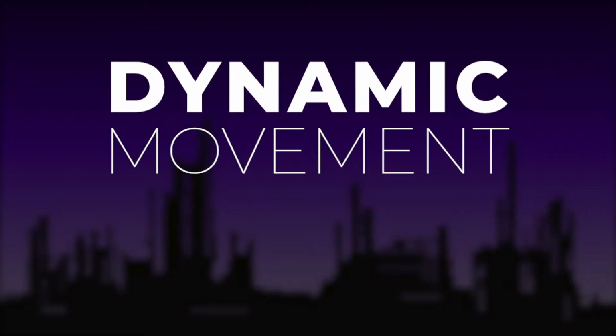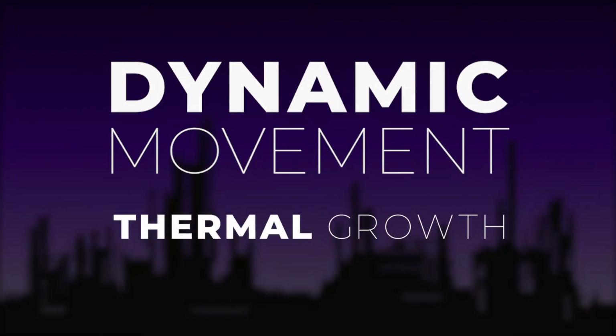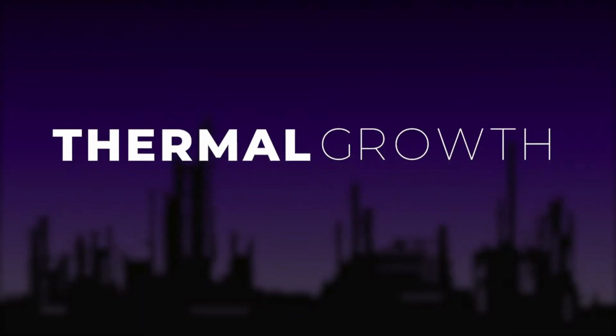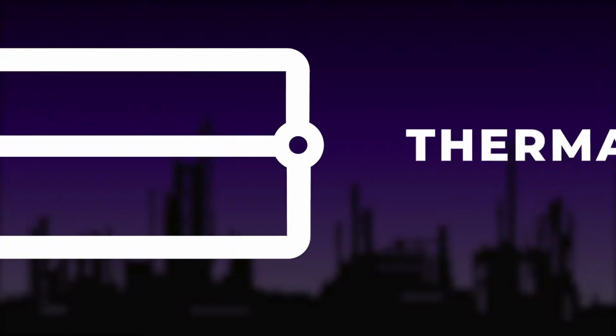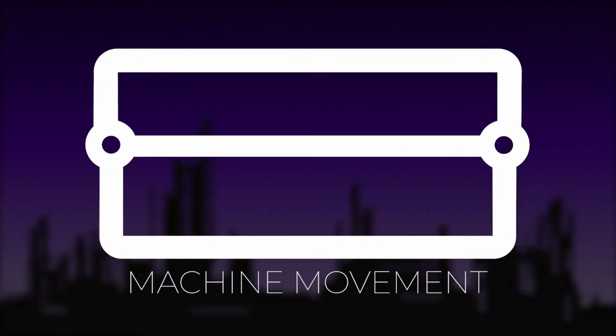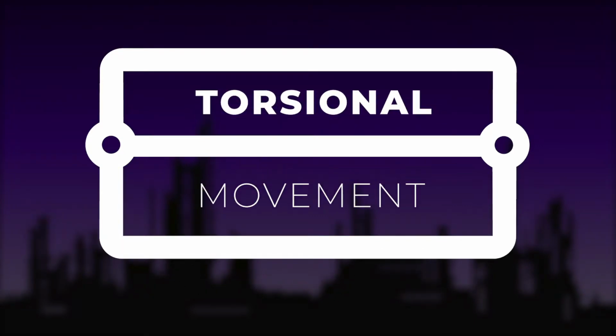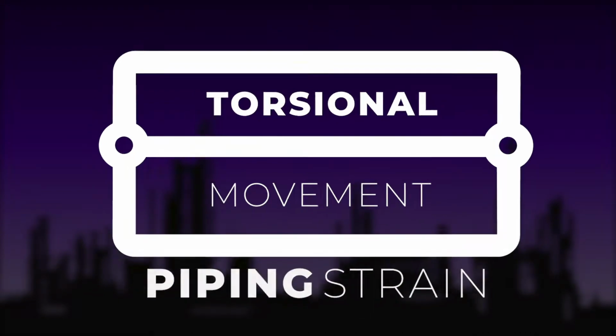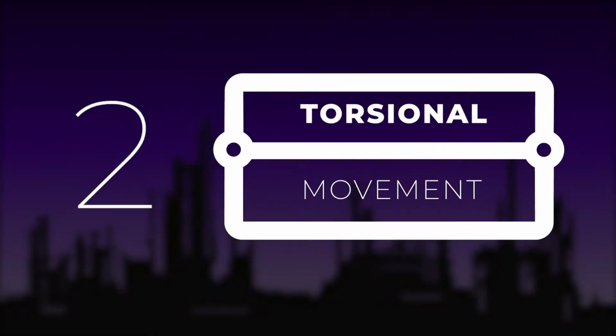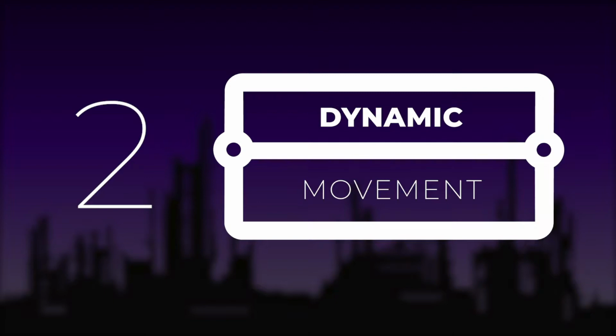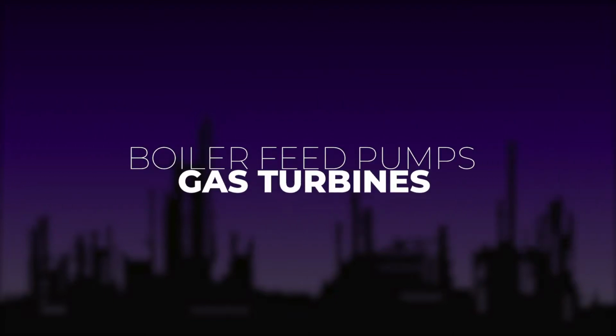Dynamic movement is also known as thermal growth. Thermal growth is a bit of a misnomer because it only describes machine movement due to thermal growth. Actually, a lot of what's thought to be seen as thermal growth is due to torsional movement of machine and piping strain.